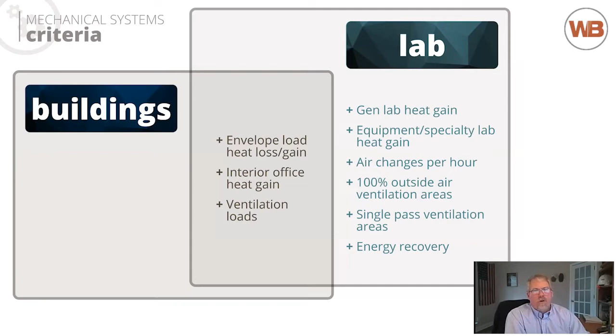When you start talking about mechanical systems to support labs and manufacturing areas, you get into much heavier mechanical system requirements that dramatically impact the physical space. If you're talking about specialty heat gain equipment, air changes, 100% outside air systems, energy recovery - where are you putting that? Is it in a mechanical space, a leased mechanical space, or a penthouse or roof space? You quickly get into a lot more building footprint requirements when you start talking about lab system mechanical infrastructure.